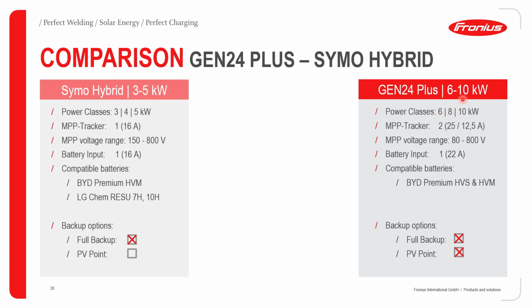So power classes range from 6 to 10. To be specific, we have the 6 kilowatt, 8 kilowatt, and then the 10 kilowatt power classes. The MPP tracker is 2, as mentioned earlier. The first MPPT, MPPT1, has an ampacity of 25 amps, and then MPPT2 has a current carrying capacity of 12.5. The MPP voltage range is from 80 to 800, and then the battery input has a current ampacity of 22 amps. Compatible batteries for now are the BYD Premium HVS and HVM batteries.